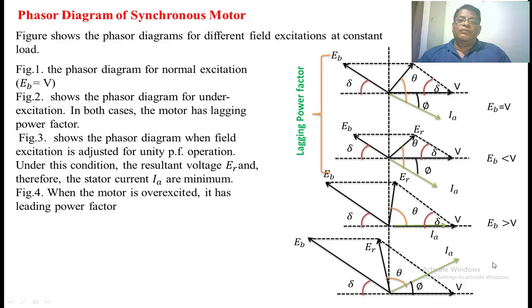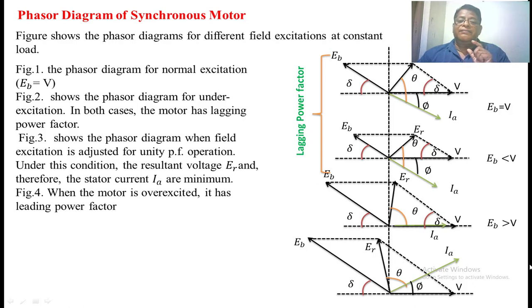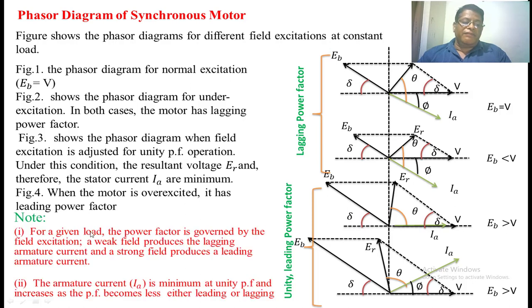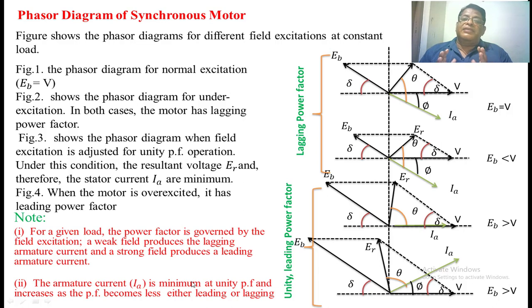By changing the field current of a synchronous motor, we can change the power factor from lagging to leading. The field current at which counter EMF equals the applied voltage is normal excitation. When the counter EMF is less than the applied voltage, it is under-excitation. When Eb is greater than V, it is over-excitation. Under excitation, the synchronous motor operates at a lagging power factor. Under over-excitation, it operates at a leading power factor. For a given load, the power factor is governed by the field excitation — a weak field current produces a lagging armature current, and a strong field current produces a leading armature current. At unity power factor, the armature current is at its minimum; during both lagging and leading conditions, the armature current increases.